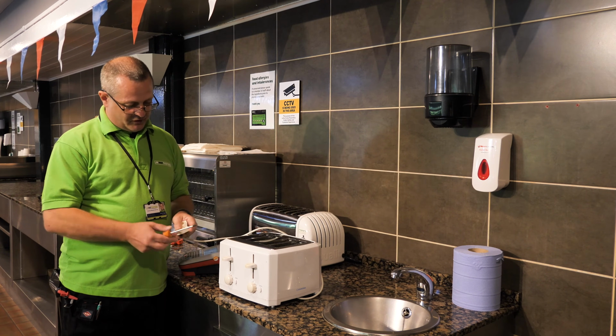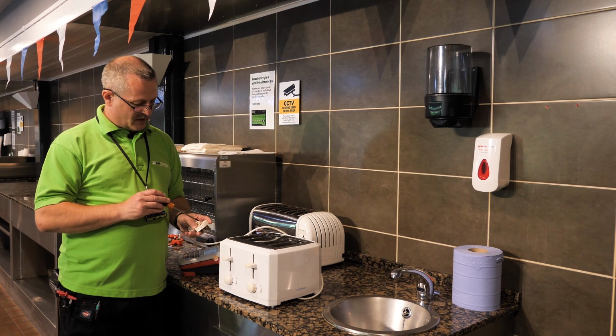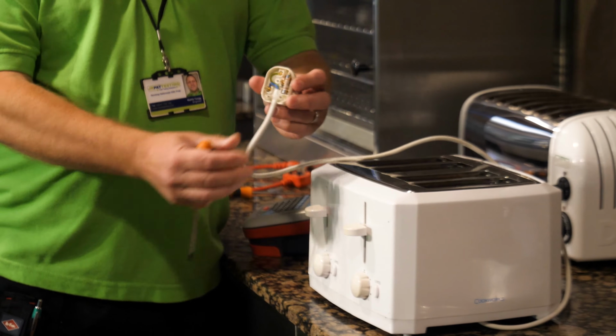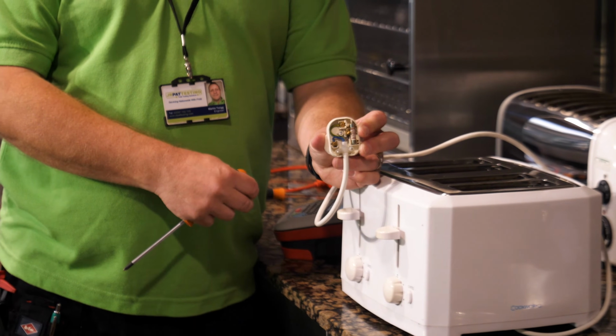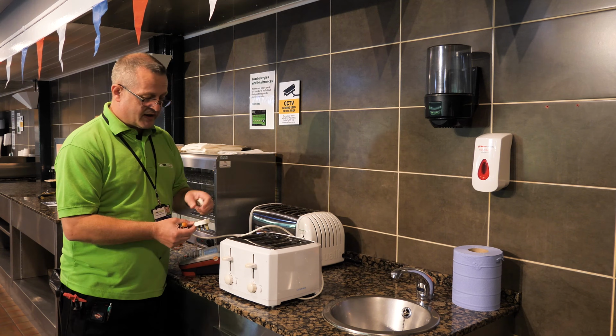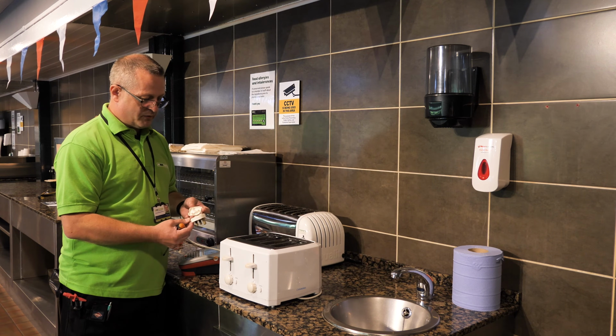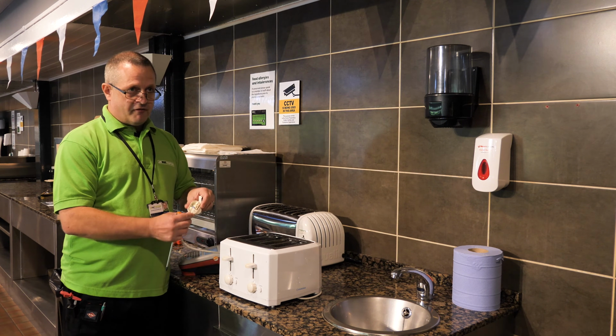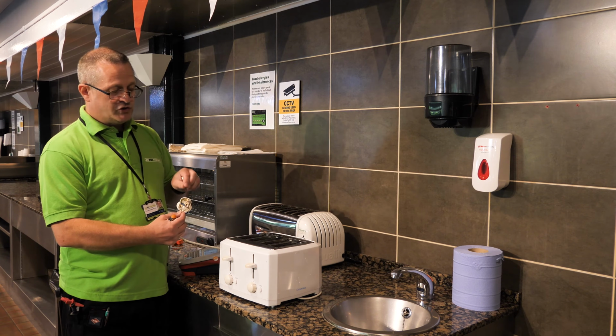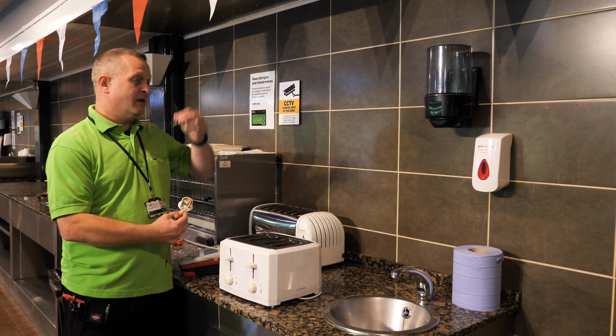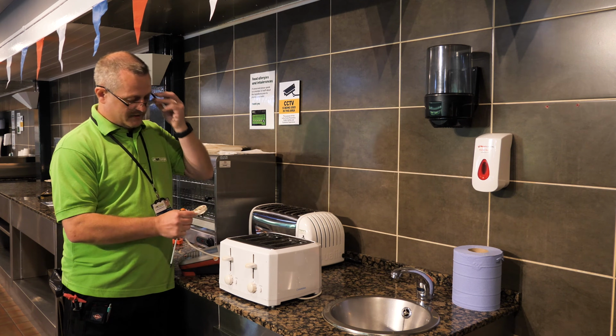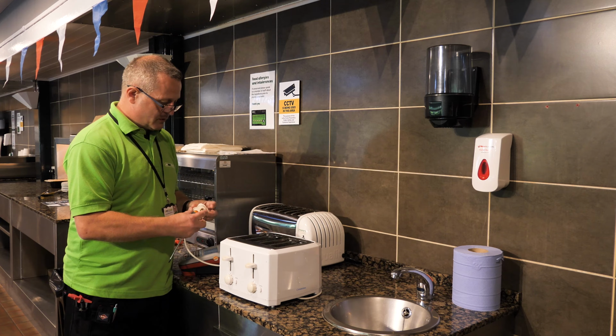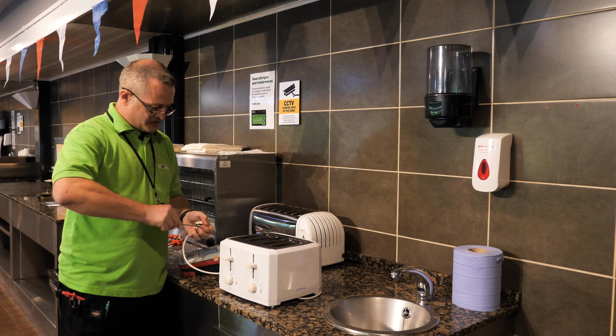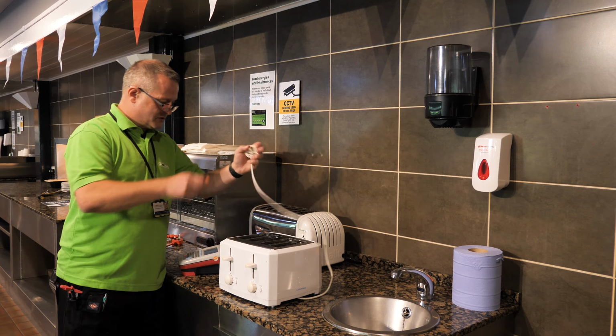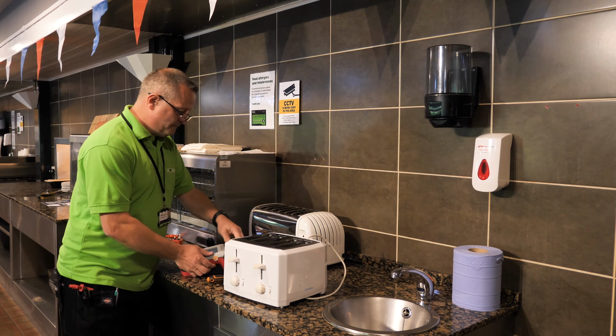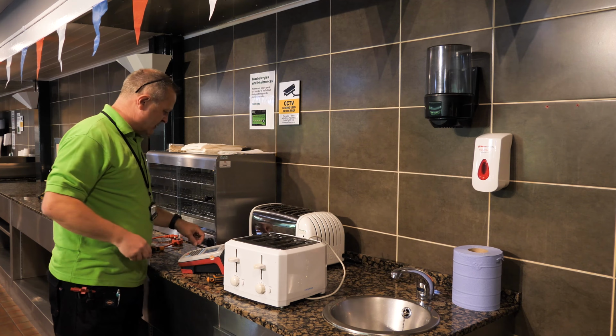First of all, just to make sure that it is correctly wired inside, no kinks, etc. And actually that is a good example of how a plug should be wired. Quite pleased with that really, and I can see that it is a 13 amp fuse. If that is untidy, we should be correcting that to make sure that it is in order once we've had a look at it. So we're going to put the plug back together, make sure it's nicely tightened up before then going to conduct the test. So I'm going to plug the appliance into the device.